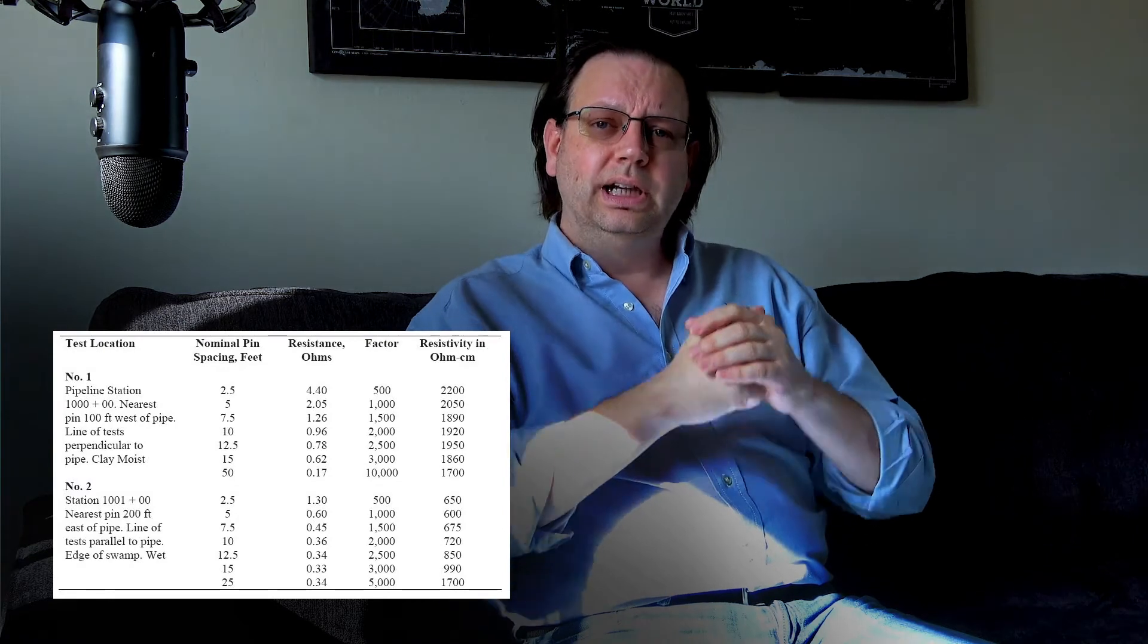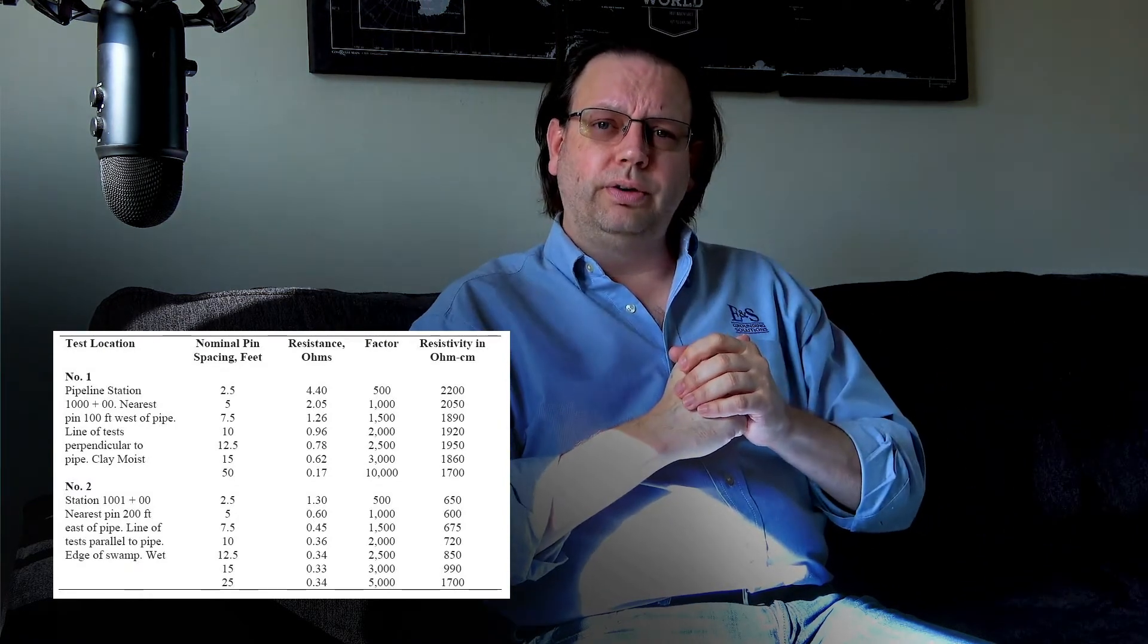That's, and we get what's called a soil model. So we can start calculating and estimating what the breaks in the layers are, that you've got a layer that's five feet thick at 100 ohm meters, and then you got another layer that's 10 feet thick at 200 ohm meters, or whatever the case is. We can actually calculate that by taking a series of different readings out across the surface of the earth.